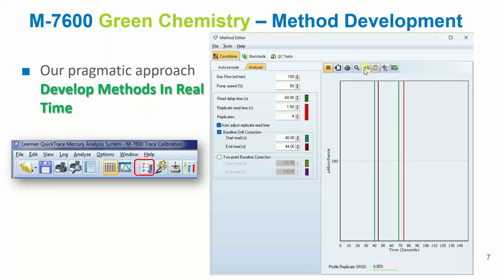Analyze a single sample. So this is the peak profile that I'm going to talk about today. This is our primary tool for method development. So it's called Analyze Single Sample. We have the stop button. It's grayed out right now since we aren't running any samples. Then we have 0, the analyzer. So that sets the detector to 0. And copy time profile to worksheet log. So I always save my final peak profile to the log. It gives you a good reference of a known good peak. You know how things were when you started out.